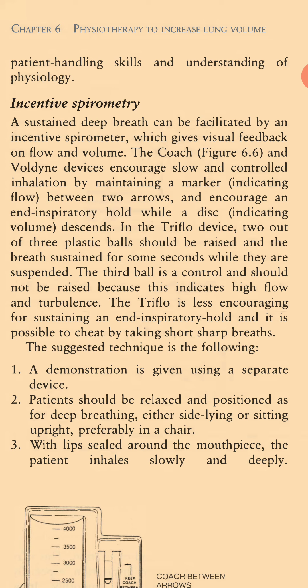In the Triflo device, 2 out of 3 plastic balls should be raised and the breath sustained for some seconds while they are suspended. The third ball is a control and should not be raised because this indicates high flow and turbulence. The Triflo is less encouraging for sustaining an end inspiratory hold, and it is possible to cheat by taking short, sharp breaths. The suggested technique is the following.